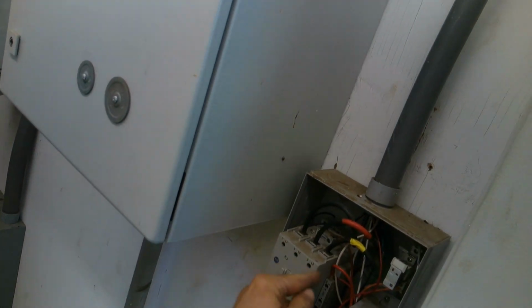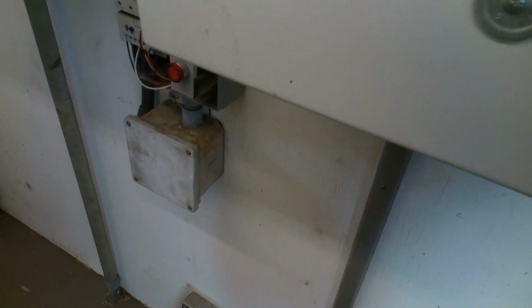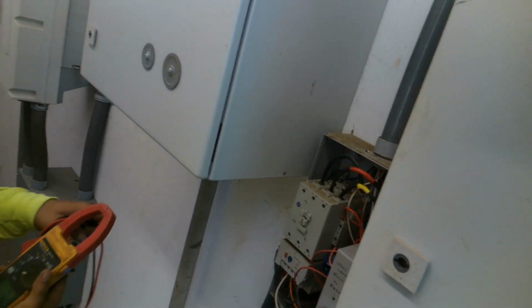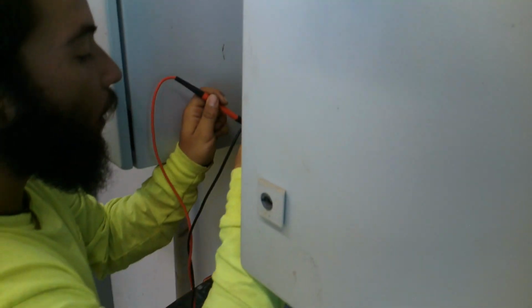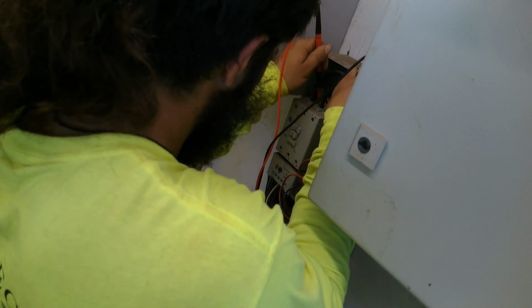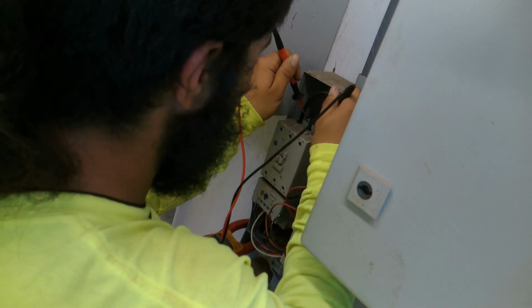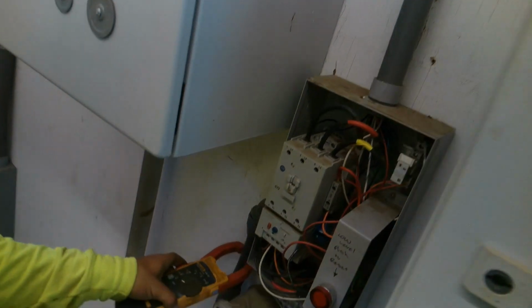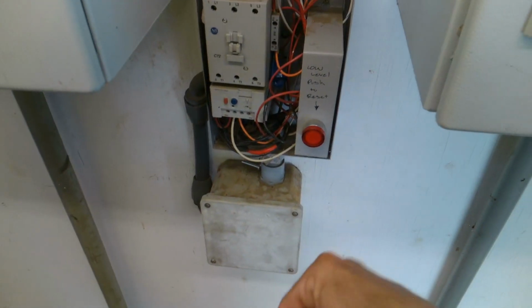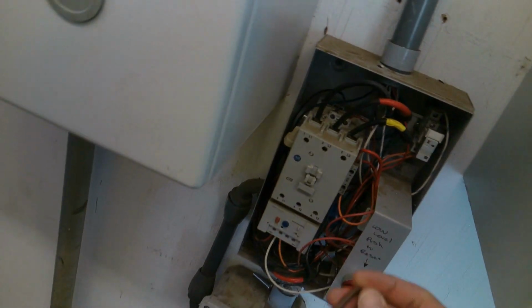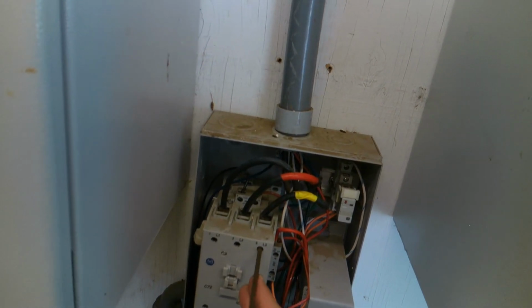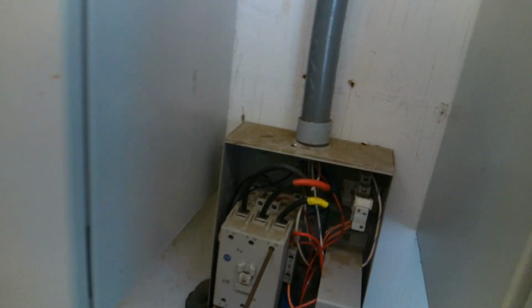What are they? Allen keys? Yeah. Check for voltage. Up here. I'm going to change 2 of these. Check for voltage, though. Verify before I go touching it with a bare Allen key. Yeah, EC. Are you touching metal? Make sure you're touching metal. Your tests are only as good as your probe. No, that's 0. Great, we're at 0. Thank you. Yeah, your tests are only as good as your probing. So if your probe is in a poor way, so is your test. Where? Oh, just the mud wasp, yeah. They're pretty minor.